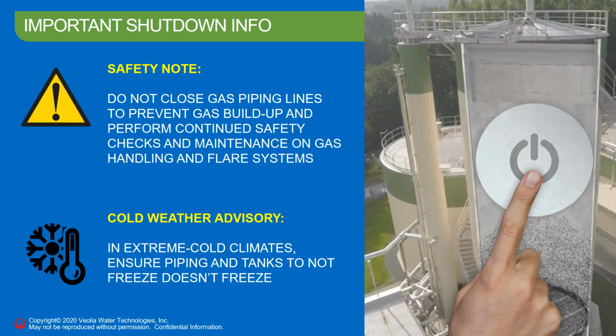The thing that you cannot and should not close are the gas piping valves, though, because even though you've digested, quote, all of the COD, there's always going to be some solids in there or some little bit of soluble COD that's going to continue to make gas even though you're shut down.